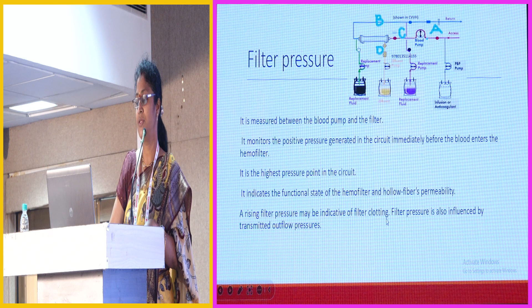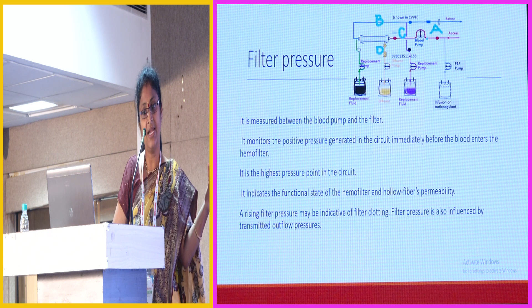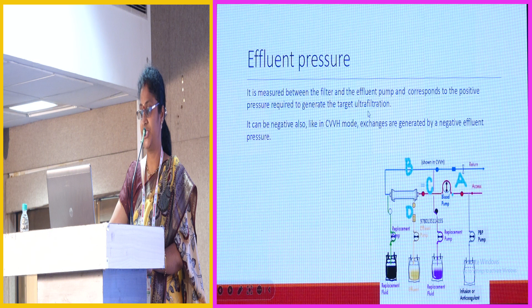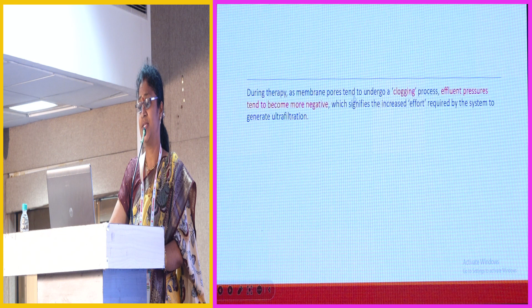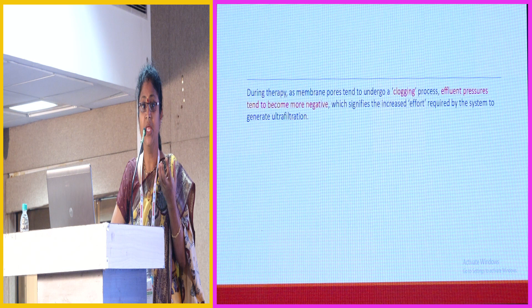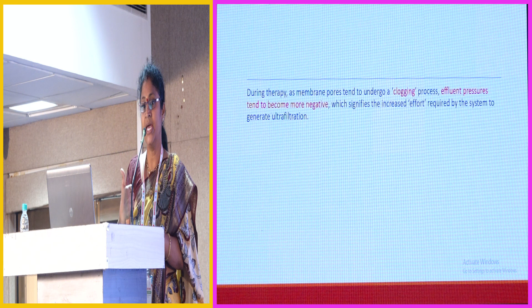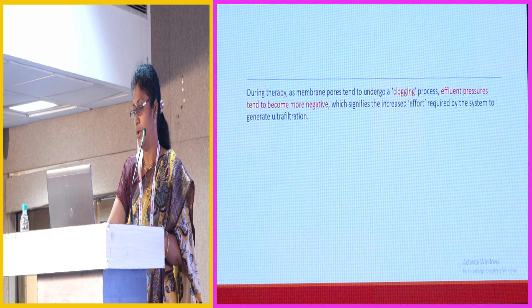It may also be influenced by the transmitted outflow pressure. Suppose you have a problem in the arterial end of the catheter, so you are getting back pressure. At that time also your filter pressure will be high. And this is the effluent pressure. It is measured between the filter and the effluent pump, and it corresponds to the positive pressure required to drive the ultrafiltration. This we have discussed. During the therapy, as the membrane pores tend to undergo clogging, the effluent pressure also tends to become more and more negative. That means you need to work more to draw the same amount of fluid. So if the effluent pressure is going high and the filter pressure is going high, that means your filter is dying. You have to prepare for changing the filter in order to decrease the downtime on CRRT.